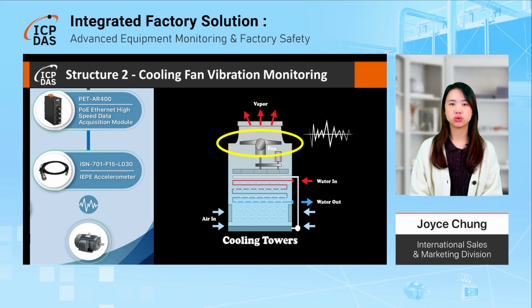In Section 2, the customer used ICP-DAS PETAR400 PoE Ethernet high-speed data acquisition module to retrieve the vibration data from the cooling fan system's gearbox and motor, collected by the IEPE accelerometer.